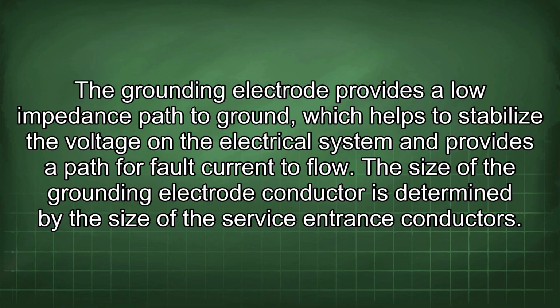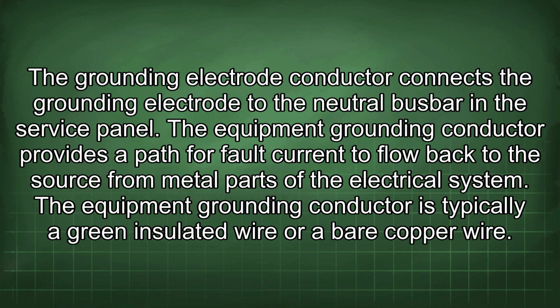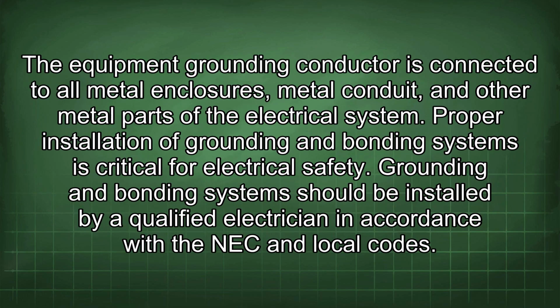The size of the grounding electrode conductor is determined by the size of the service entrance conductors. The grounding electrode conductor connects the grounding electrode to the neutral busbar in the service panel. The equipment grounding conductor provides a path for fault current to flow back to the source from metal parts of the electrical system. The equipment grounding conductor is typically a green insulated wire or a bare copper wire. The equipment grounding conductor is connected to all metal enclosures, metal conduit, and other metal parts of the electrical system.